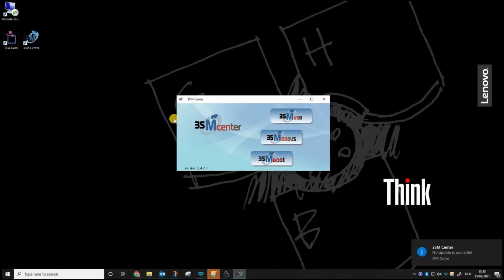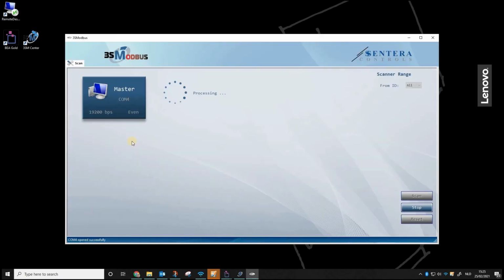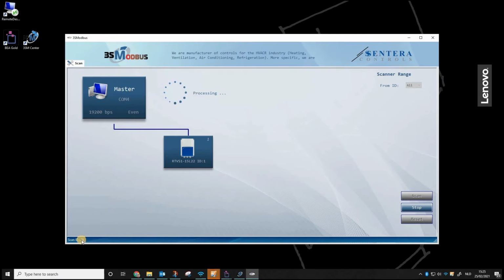We start the 3S Modbus 3SM Center software suite. If you are connected to the internet, it will check if there is an update available. Then we start 3S Modbus. 3SM boot is used to update the firmware of your device. The system will automatically scan for all available IDs and will immediately find the device on ID 1. This is the factory setting of all our devices. We have found our RTVS, so we can stop the scanning.